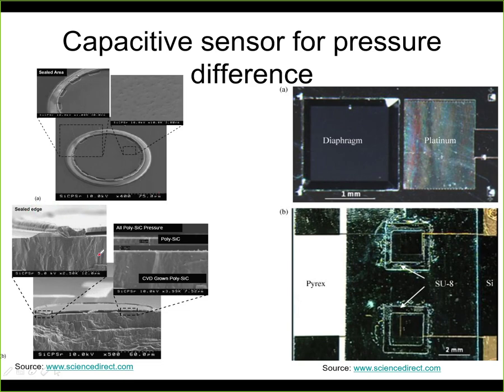And here we can see the view when you cut through the material. And we can see that here this is the diaphragm itself. This is the hole under the diaphragm, so the diaphragm is changing its shape like this. You can see it here. This is the sealed edge of the diaphragm, and this is the cavity under it. And we can evaluate by capacitive changes or by installing strain gauges on the diaphragm the actual pressure that we measure.